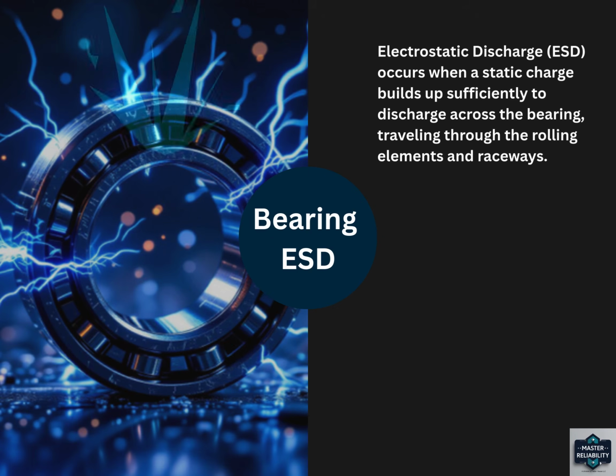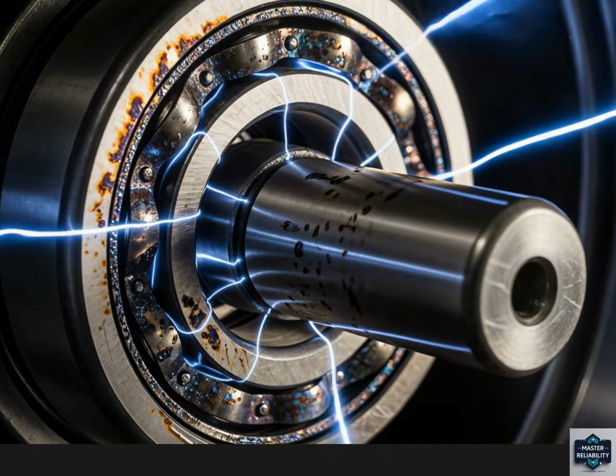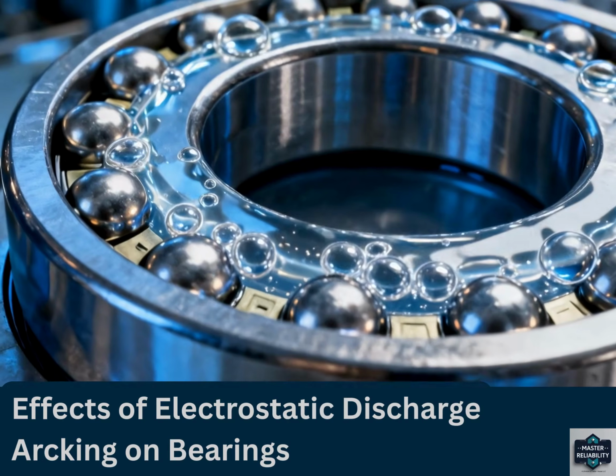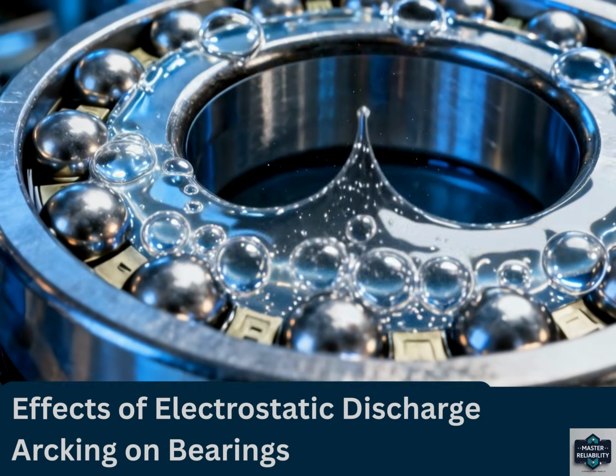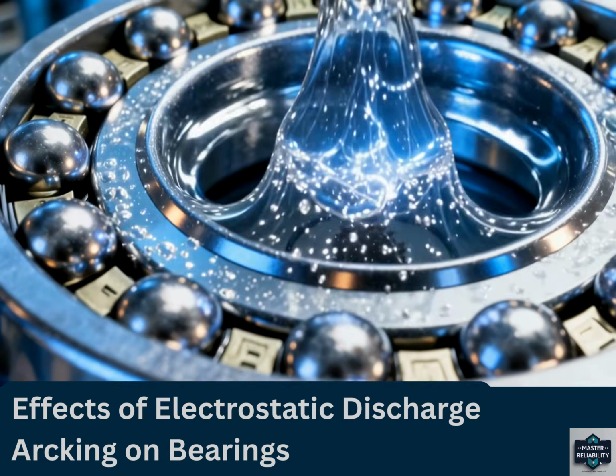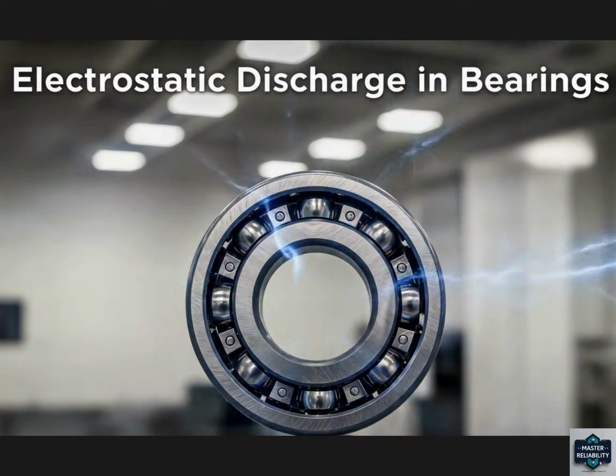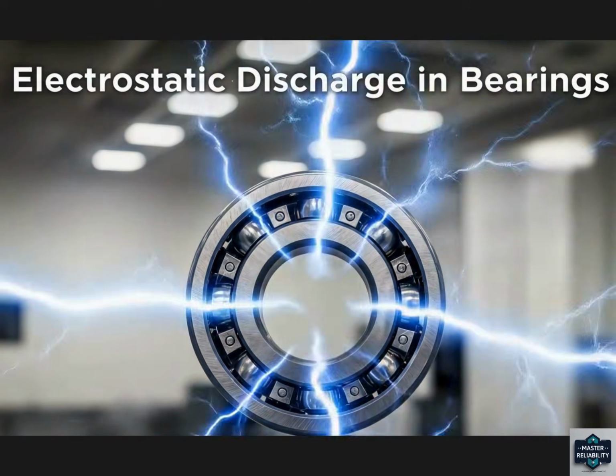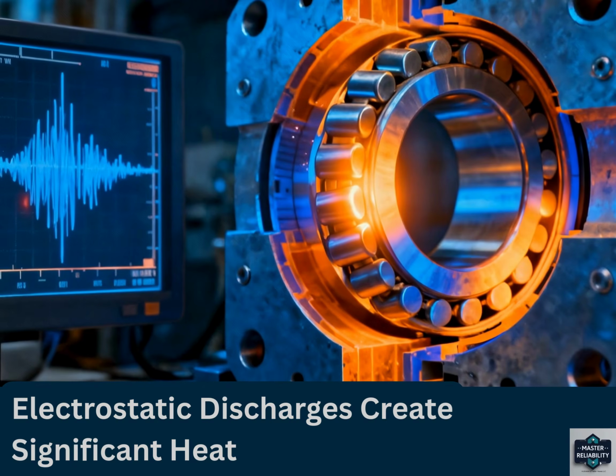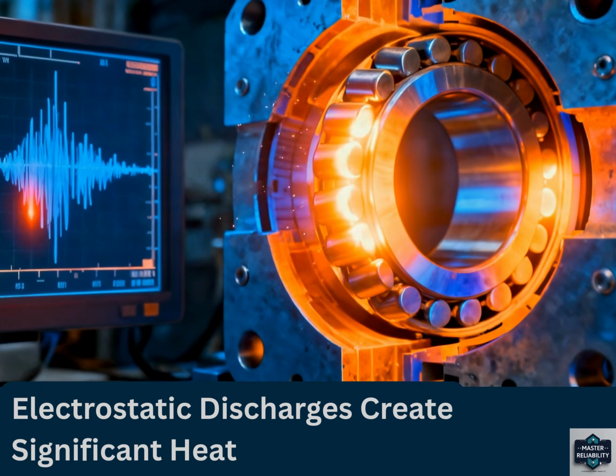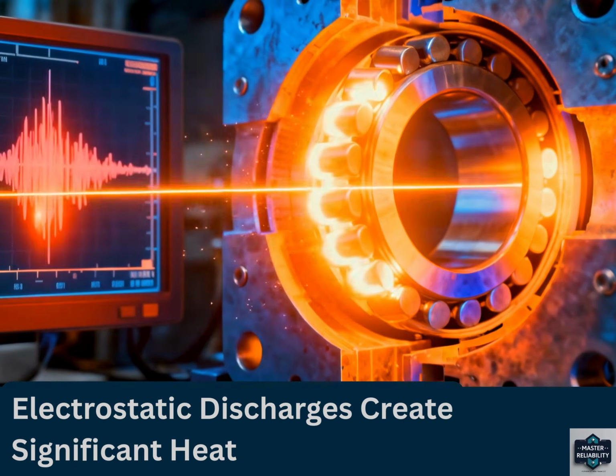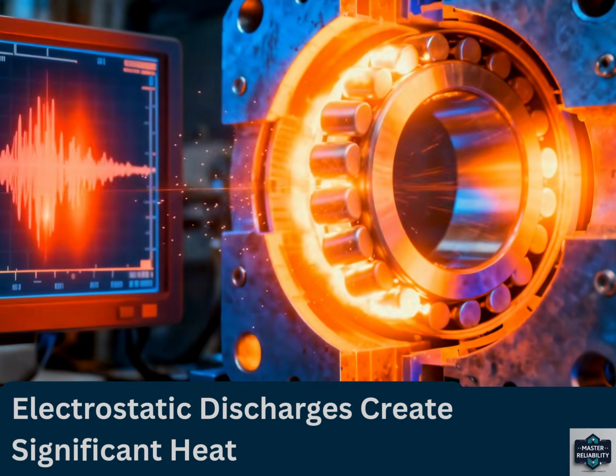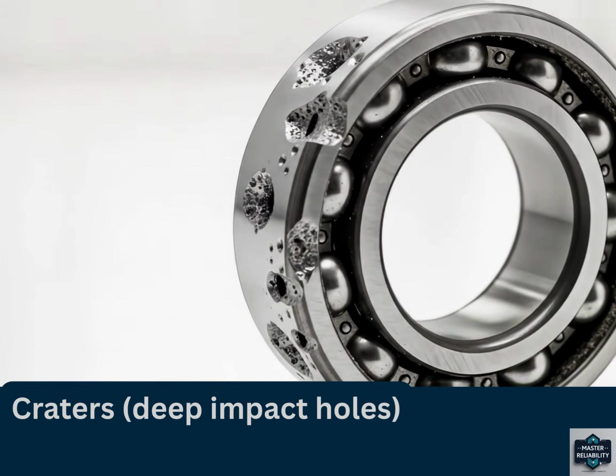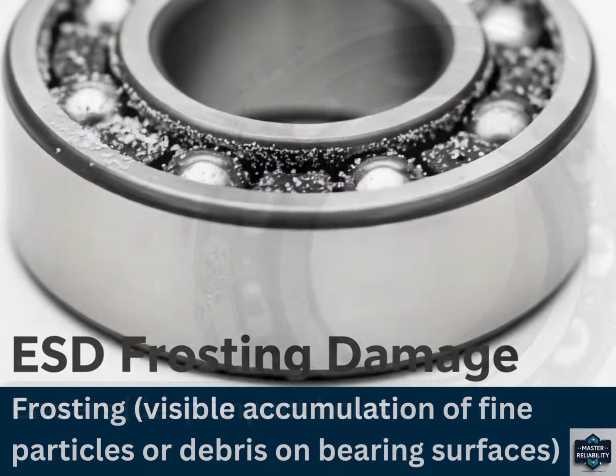Electrostatic discharge, or ESD, occurs when a static electrical charge builds up and discharges across a bearing, traveling through the rolling elements and raceways. This discharge creates microscopic electrical arcs at contact points. These arcs generate intense localized heat that briefly melts the metal surface.